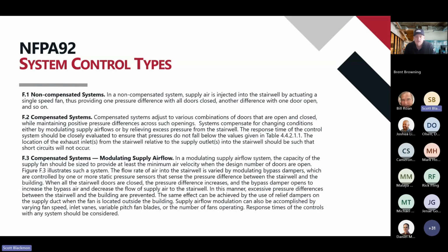The next is a compensated system. So that's basically going to be a set speed fan, but you're going to have a relief damper or something in there that relieves some of those pressure spikes as you see when your doors open and close. And then a compensated system with modulating airflow. That's really the type of system that's going to actually monitor the pressure inside the stairwell. It's going to keep that stairwell at pressure at all times.